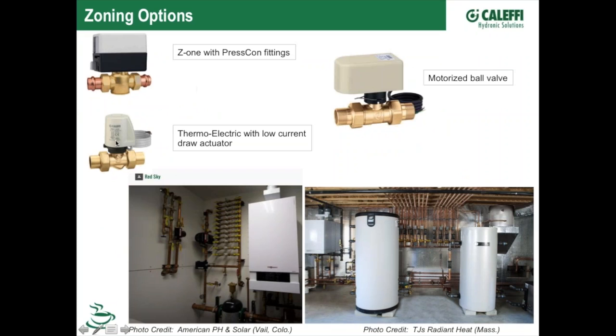In some cases, people want a slower action valve. This is a thermo-actuated zone valve here. And over here, we've got basically a ball valve with a motor, a motorized ball valve, high flow rates there, high shut-off pressure. Different applications for these valves. It just depends on what type of flow rate you're trying to shut off, what you're expecting the system to do. But I think we've got a solution for probably pretty much any zoning application you might have. And again, some more nice pictures that were sent in to us over the years in our excellence program, showing how the zone valves have been added to systems.